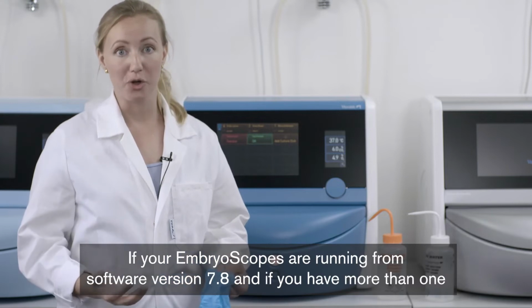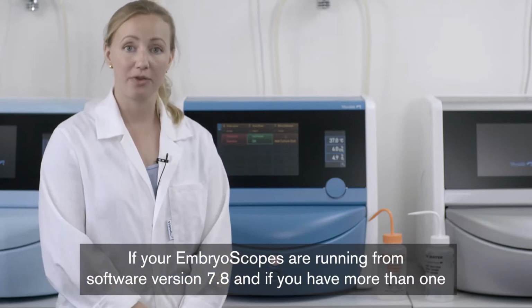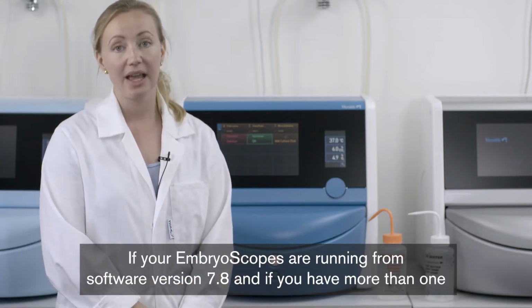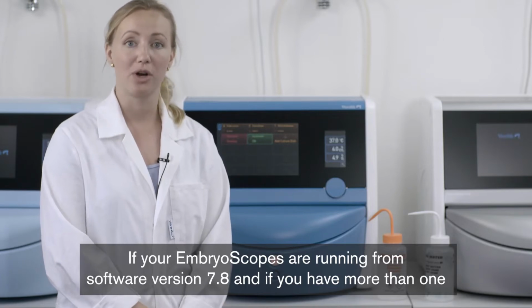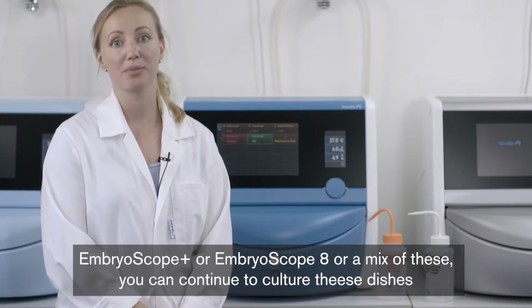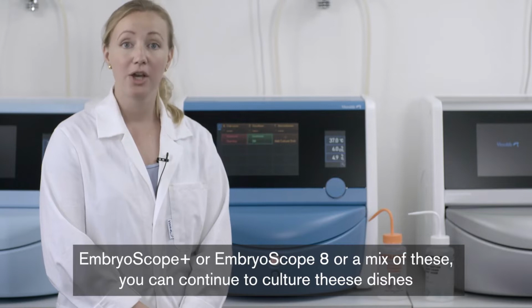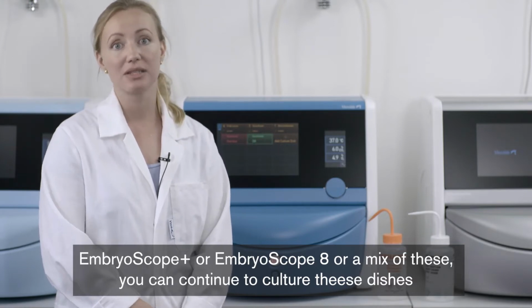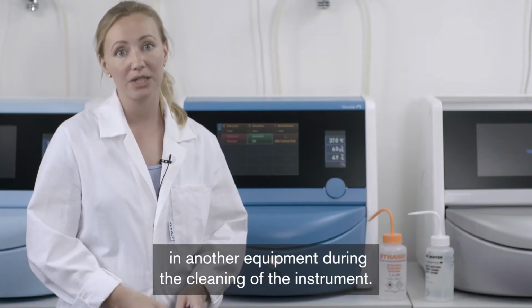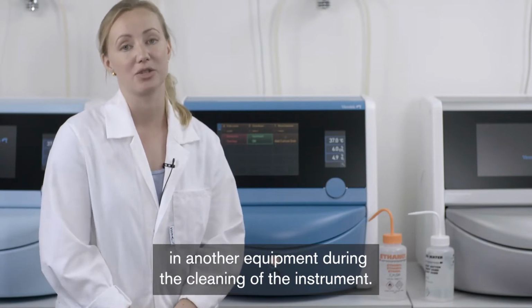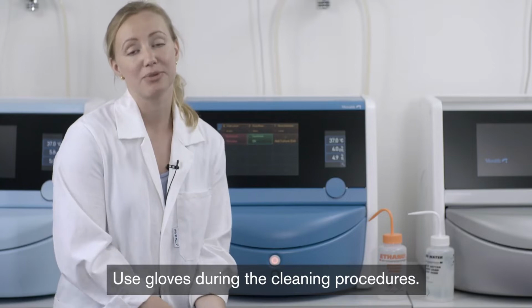If your EmbryoScopes are running from software version 7.8, and if you have more than one EmbryoScope Plus or EmbryoScope 8, or a mix of these, you can continue to culture these dishes in another piece of equipment during the cleaning of the instrument. Use gloves during the cleaning procedures.